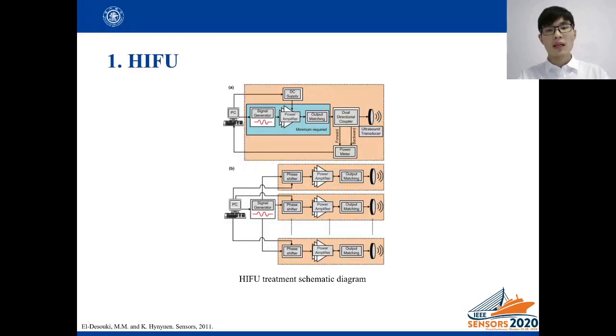First of all, let me introduce the background knowledge and principle of HIFU. HIFU focuses multi-array ultrasonic beams on the target area. Increased focal temperature results in coagulation necrosis of cells. The focus of HIFU is not fixed. It can be deflected by phase modulation.